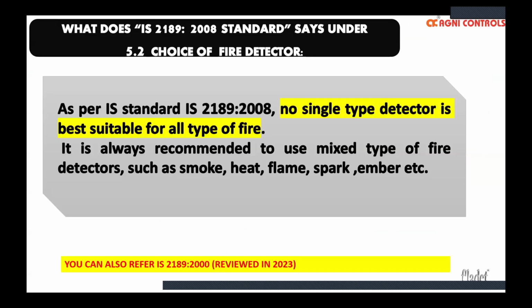IS 2189 is the Indian standard for fire alarm systems that we are following in the nation right now. So what does the standard say? It says that no single type of detector is best suitable for all types of fire. Basically, the designer has to choose the right detector for the right application, and not just smoke detectors for any application. A mixed type of detector shall be used for effective fire detection capability. That is what IS 2189 states.